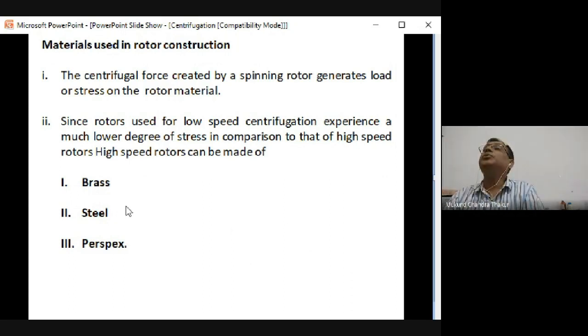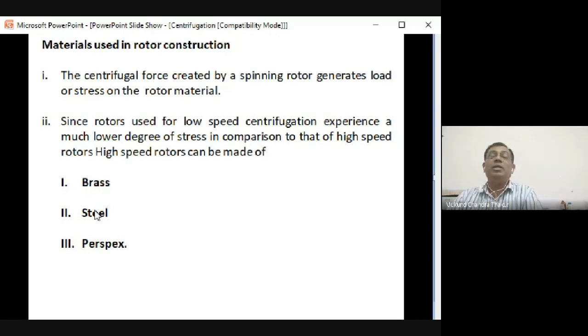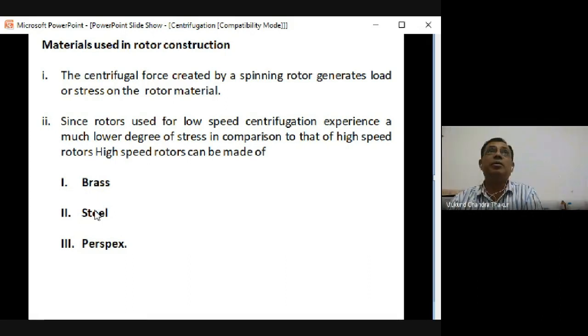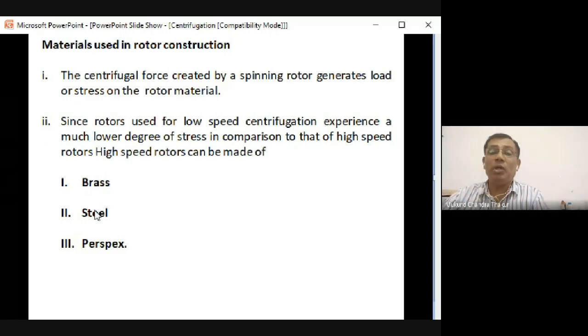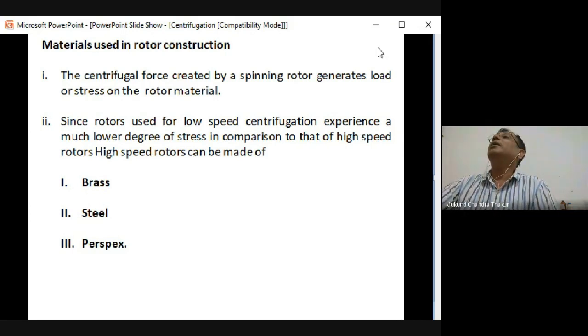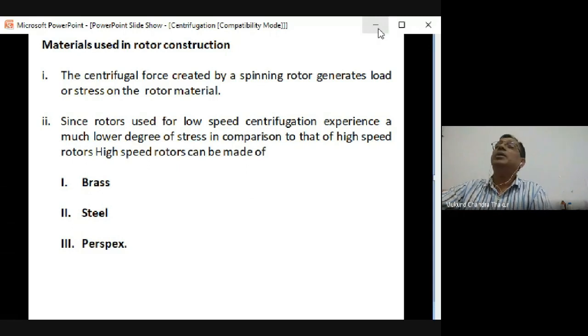The motor rotors of centrifuge can be made of brass, steel, Perspex, aluminium, or titanium. If the rotor is heavier, the motor has to work more and will give less RPM. When replacing a rotor from a lighter to a heavier one, you will experience less RPM.